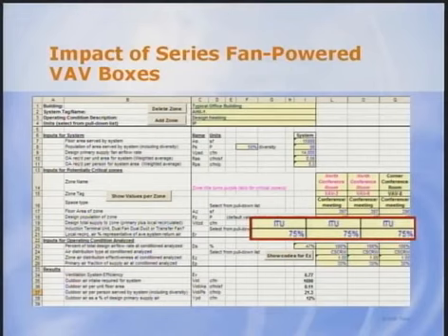ASHRAE recently finished a research project on E sub R and found that it varied, as expected, depending on the location of the box inlet relative to the space served by the terminal. Typical design values will vary from 0.5 to 1. Refer to the ASHRAE Research Project 1276 for details. In this case, we have assumed that E sub R is 75%.